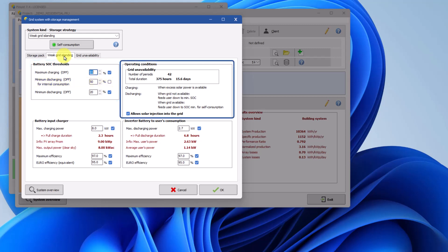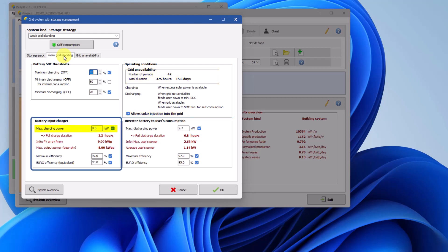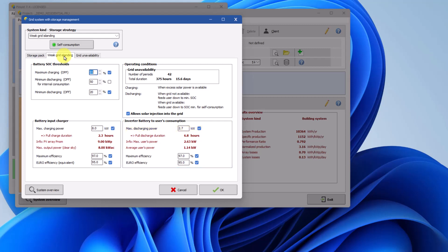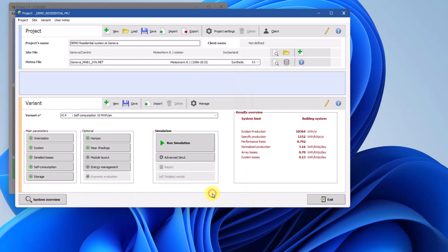In the Operating Conditions box, you can find information about grid unavailability. You can choose whether to inject energy into the grid, or to use the grid only to cover the load profile, typically at night. The Battery Input Charger box allows you to define the maximum charging power, ensuring it respects the battery's maximum charging capabilities. Similarly, the Inverter Battery to user's consumption box lets you define the maximum discharging power of the battery. This value should be lower than the charging power. Consult your battery datasheet to determine the appropriate value. Once the grid islanding scenario is configured, click OK to continue and run the simulation.